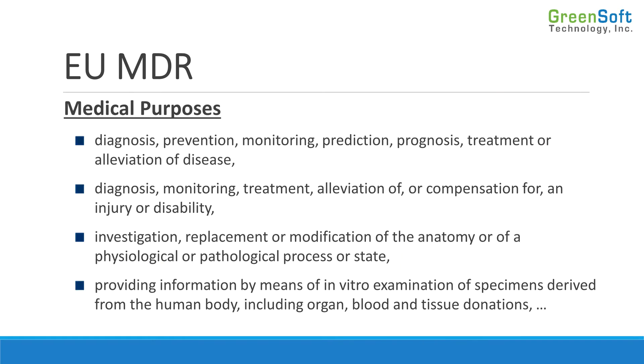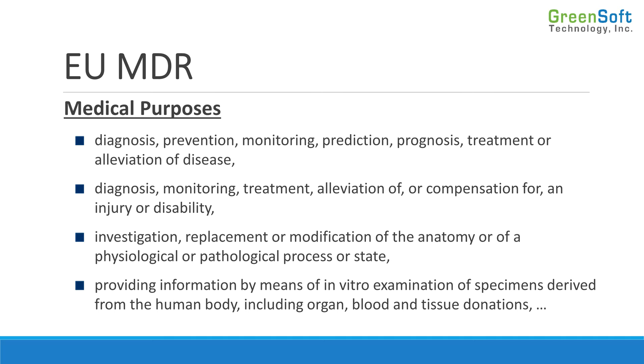Here are the medical purposes that bring a device into scope. If the device is used to diagnose, prevent, monitor, predict, or treat a disease or other ailments, then it's a medical device. If it's used to diagnose, monitor, treat, or otherwise address an injury or a disability, it's also a medical device. If it's used to investigate, replace, or modify the anatomy or a physiological or pathological process or state in the body, then it's also a medical device. And if it's any device that examines blood, tissue, etc. from the human body, it is also a medical device.